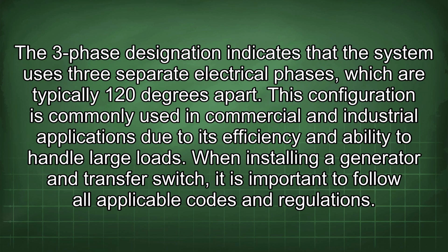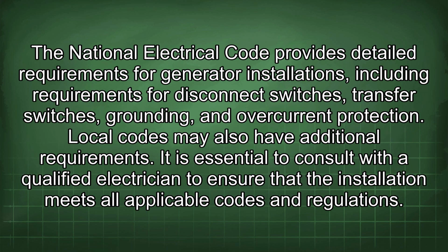The three-phase designation indicates that the system uses three separate electrical phases, which are typically 120 degrees apart. This configuration is commonly used in commercial and industrial applications due to its efficiency and ability to handle large loads. When installing a generator and transfer switch, it is important to follow all applicable codes and regulations. The National Electrical Code provides detailed requirements for generator installations, including requirements for disconnect switches, transfer switches, grounding, and overcurrent protection. Local codes may also have additional requirements.